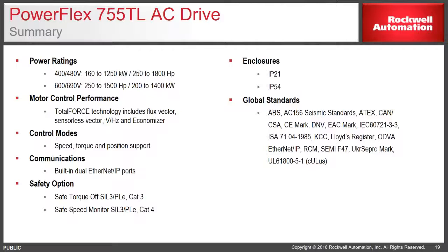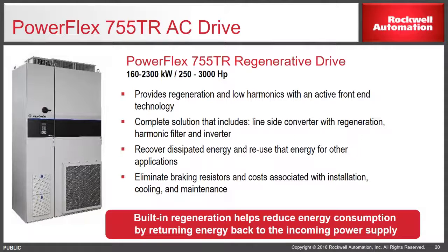The PowerFlex 755TR is available from 250 to 3,000 horsepower. It provides regeneration and low harmonics with an active front end. It's a complete solution that includes line-side converter with regeneration, harmonic filter, and an inverter. You can recover dissipated energy and reuse that energy for other applications. It eliminates braking resistors and the costs associated with them.